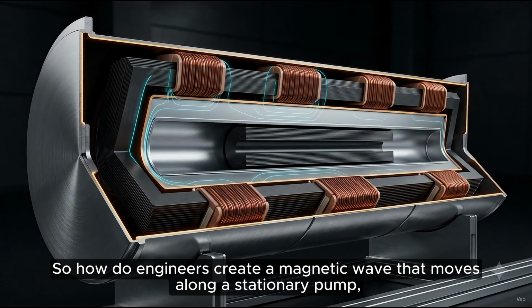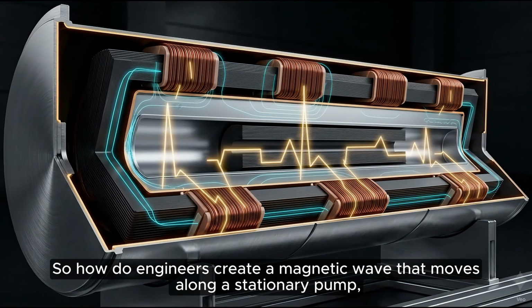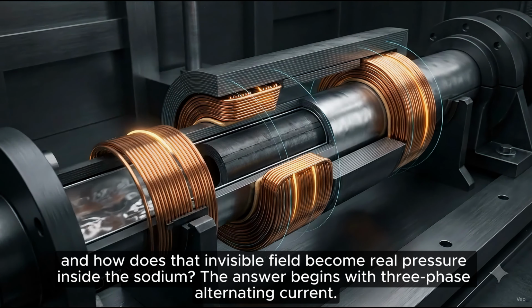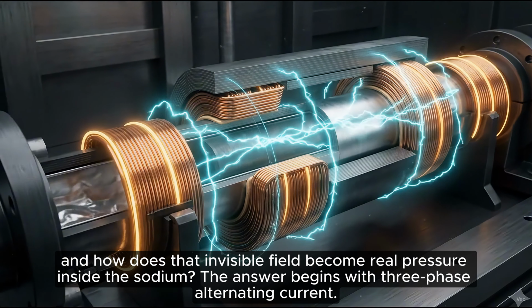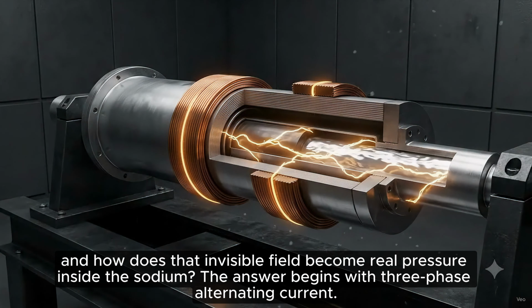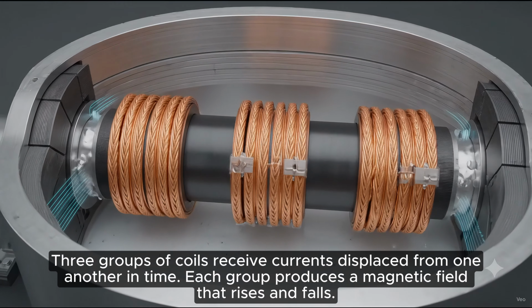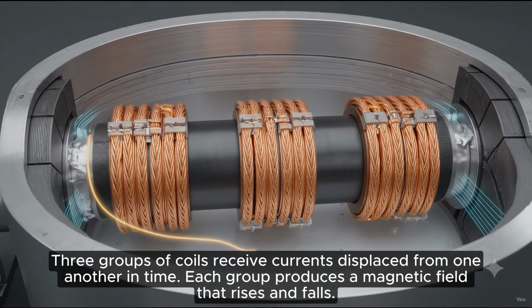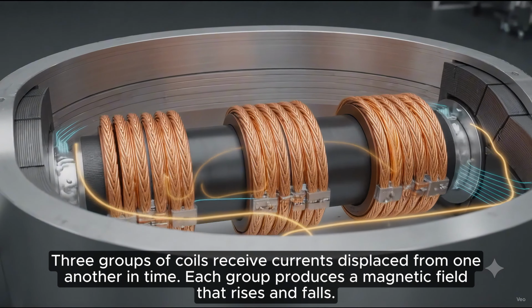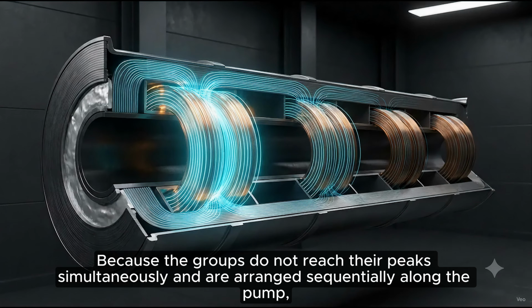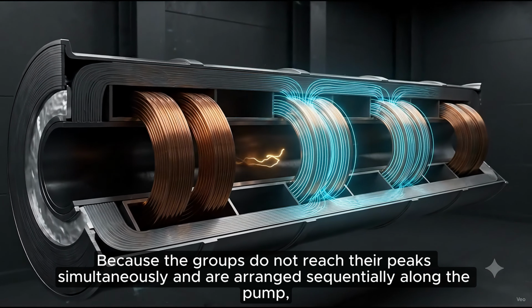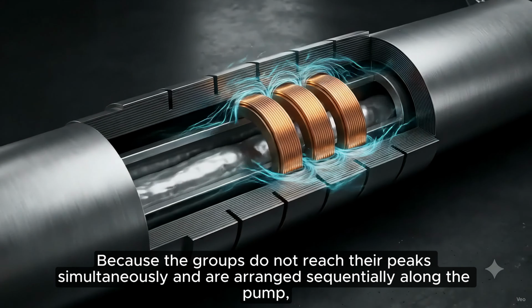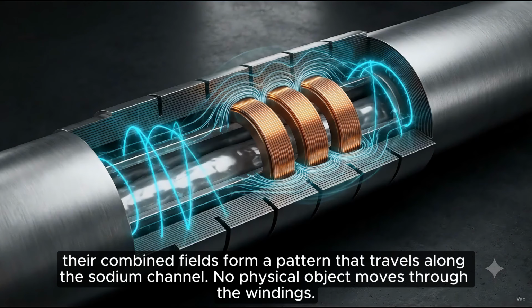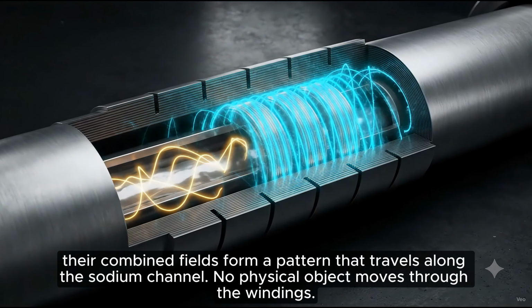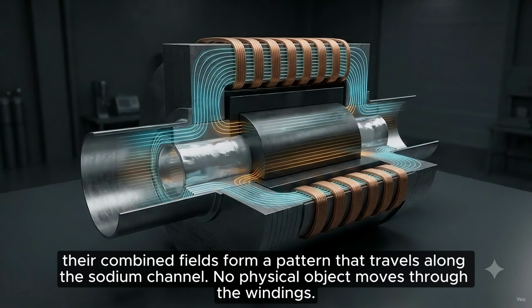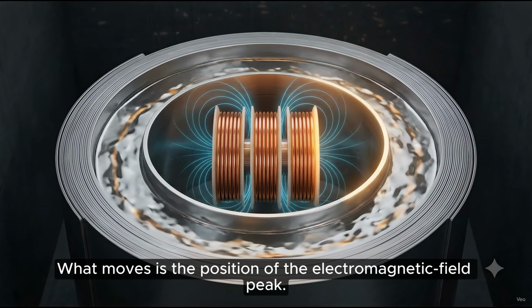So how do engineers create a magnetic wave that moves along a stationary pump? And how does that invisible field become real pressure inside the sodium? The answer begins with three-phase alternating current. Three groups of coils receive currents displaced from one another in time. Each group produces a magnetic field that rises and falls. Because the groups do not reach their peak simultaneously and are arranged sequentially along the pump, their combined fields form a pattern that travels along the sodium channel. No physical object moves through the windings. What moves is the position of the electromagnetic field peak.